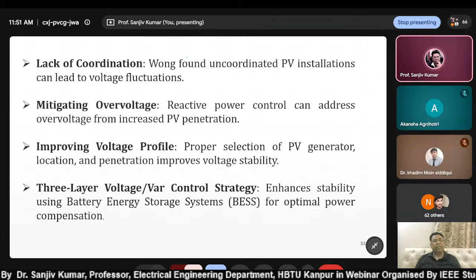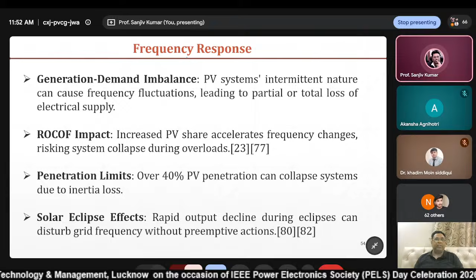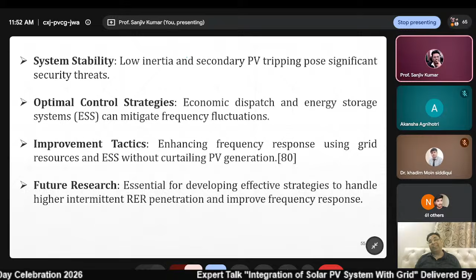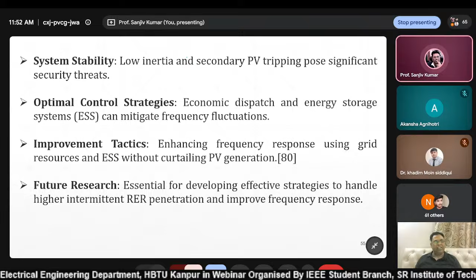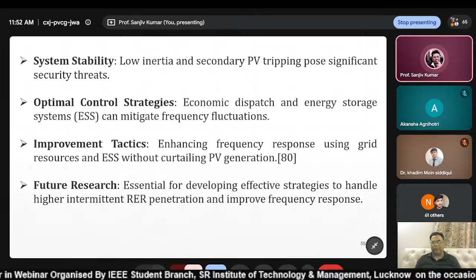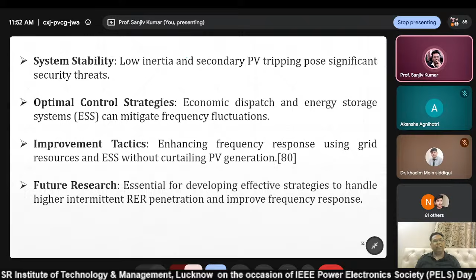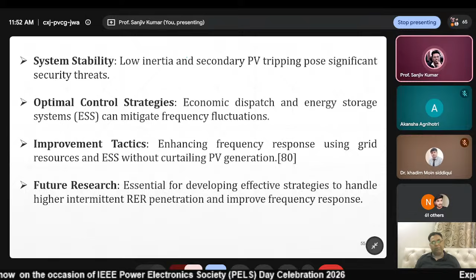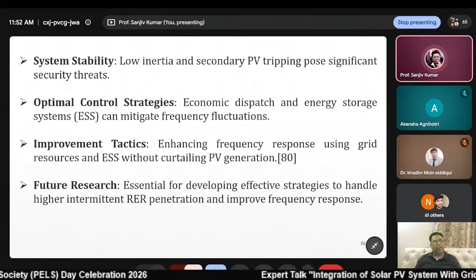Now, if we talk about frequency response, then generation demand imbalance and ROCOF impact, penetration limit, and solar eclipse effects are all common effects of frequency related issues. These are the things you should consider. Then system stability. See, low inertia and secondary PV tripping pose significant security threats. We are installing very tiny, very small PV systems, right? So their inertia, or stability against overloading, is very, very low. That should be taken care of, so that it does not trip the system, right? And we should use an optimal control strategy. That means keeping MPPT, and the frequency fluctuation should not be there.